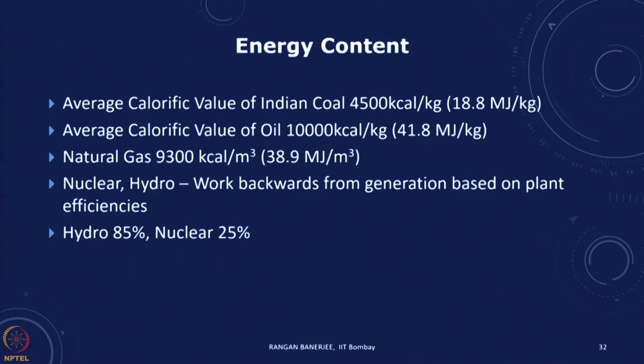In the case of nuclear and hydro it is very difficult to talk about the amount of flow of water, but what we know is the generation from hydro plants and we work backwards using the efficiency. A hydro plant efficiency is of the order of 85 percent, nuclear of 25 percent, and then you can get what the energy content is.